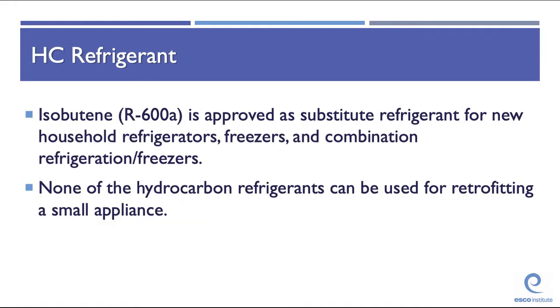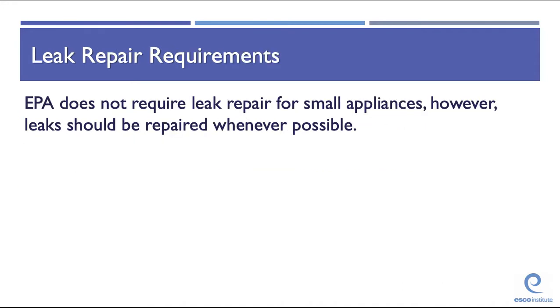Hydrocarbon refrigerant R-600A (isobutane) is an approved substitute refrigerant for new household refrigerators, freezers, and combination refrigerator-freezers. None of the hydrocarbon refrigerants can be used for retrofitting small appliances. EPA does not require leak repair for small appliances, but leaks should be repaired whenever possible to conserve refrigerants. Make sure valve cores are tight and caps are on the Schrader ports to prevent accidental depression and leaking from the valve cores.